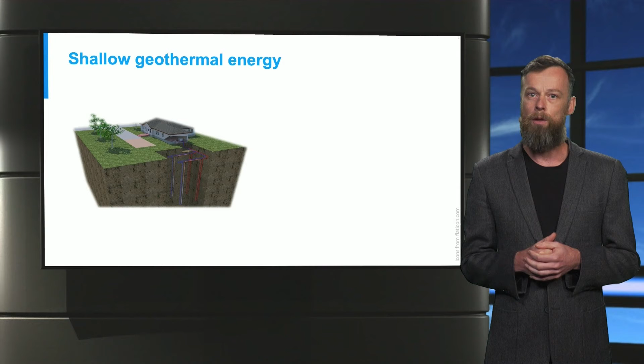Shallow geothermal energy is a small-scale system which can vary its response to demand. It takes advantage of the relatively stable temperature a few meters below the surface, and the system can provide heating and cooling from the shallow subsurface, which is at a low temperature. Due to this low temperature, the source needs to be close to the demand and requires the use of a heat pump for heating and often also for cooling.